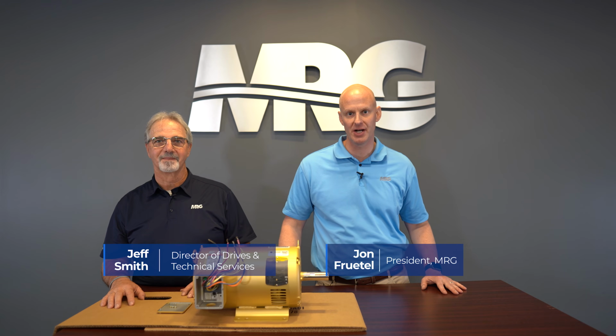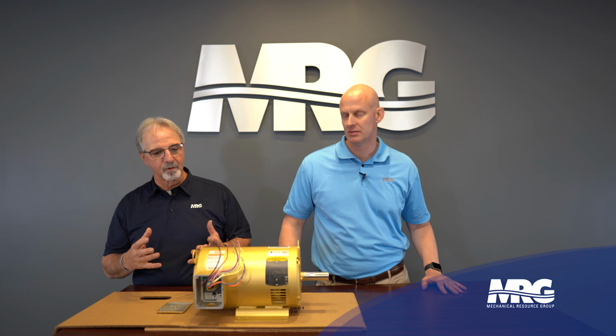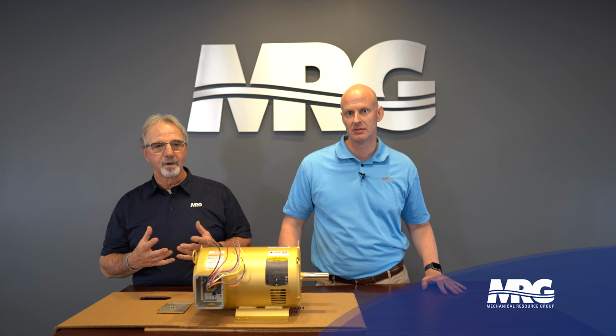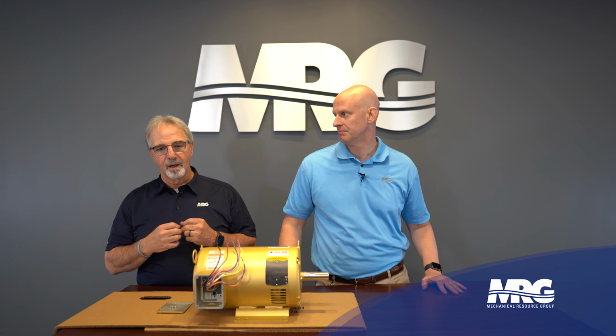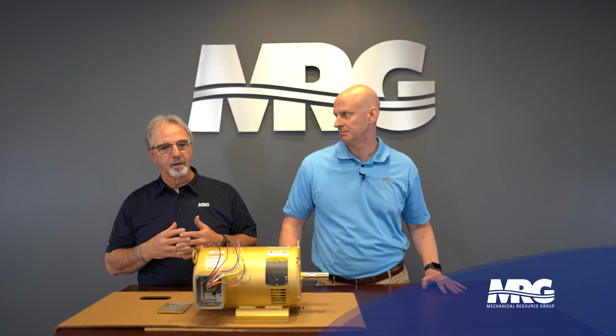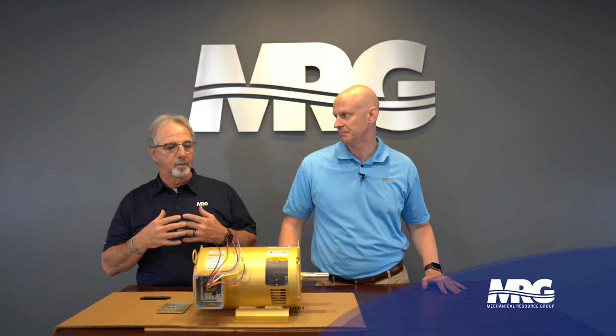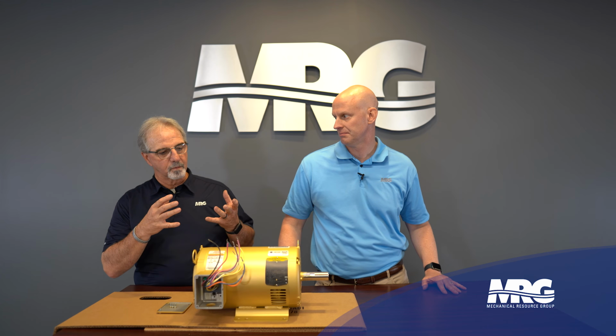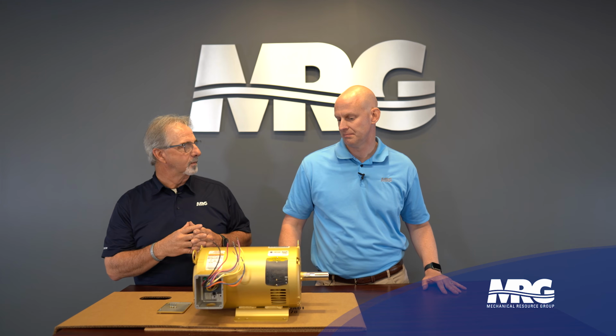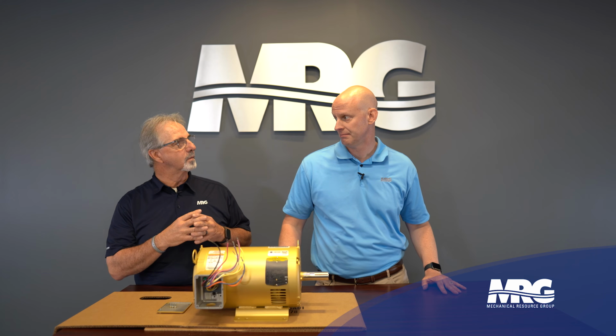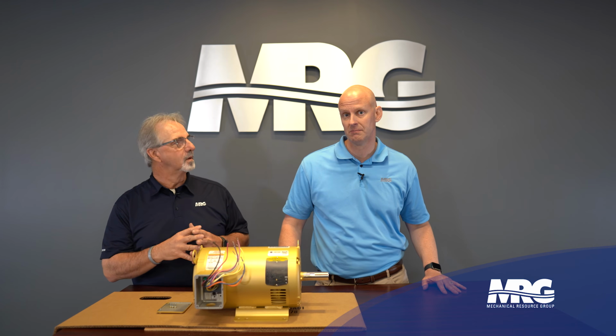Today we got a good one. We're talking about motors, how to wire up a standard induction motor, primarily for a reduced voltage application, right? Correct. We're going to go through a couple of different ways for reduced voltage. We're going to do both part winding start and Wye-Delta. But what I wanted to show you first was a standard 9-lead motor. Not all motors come from the manufacturer with 9 leads.